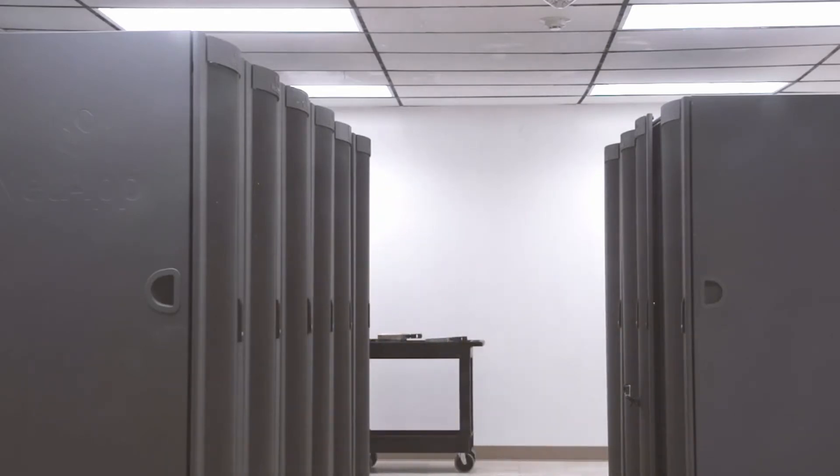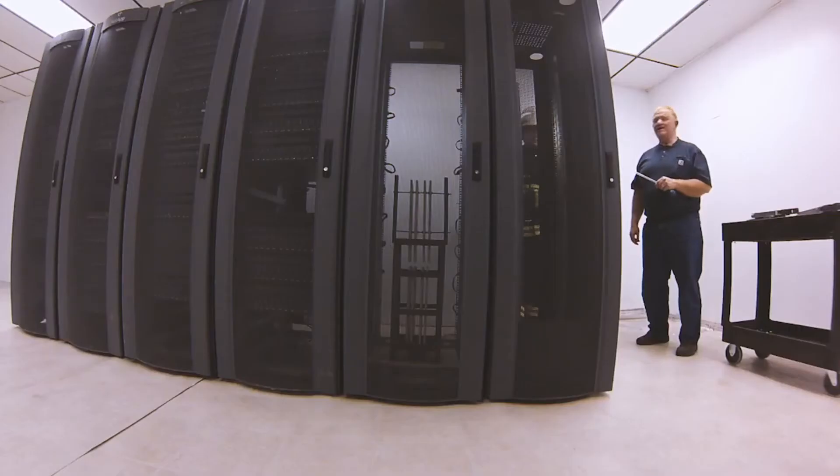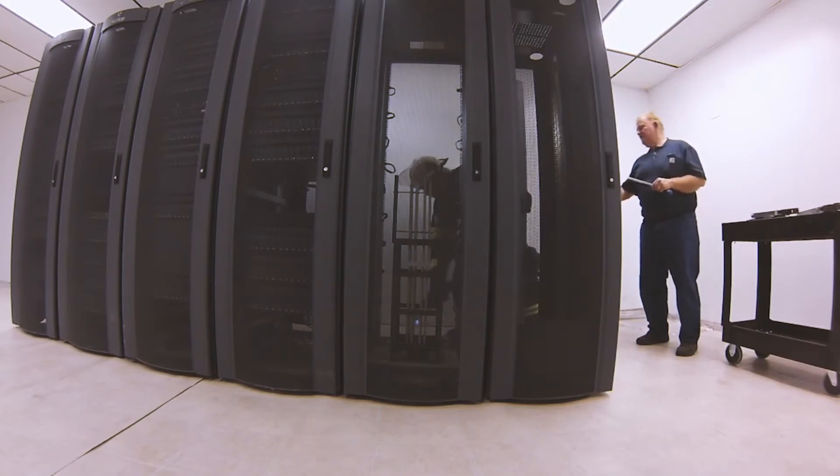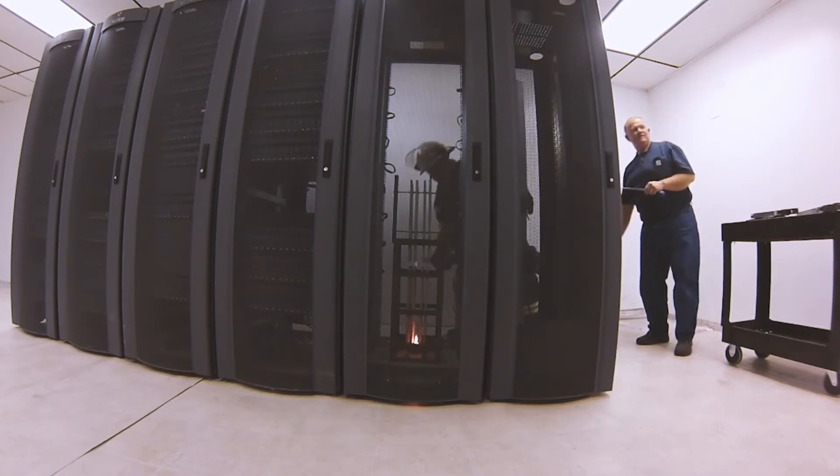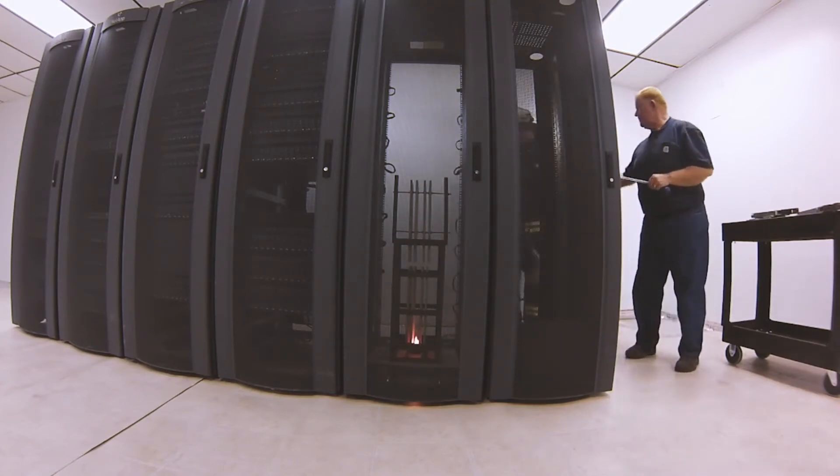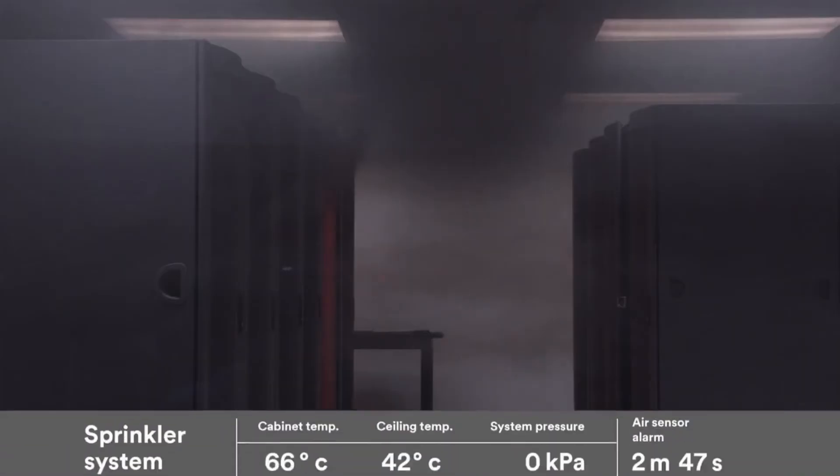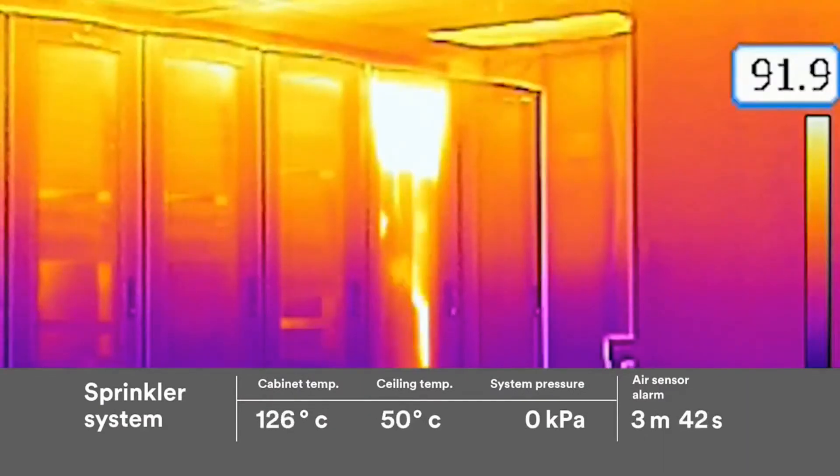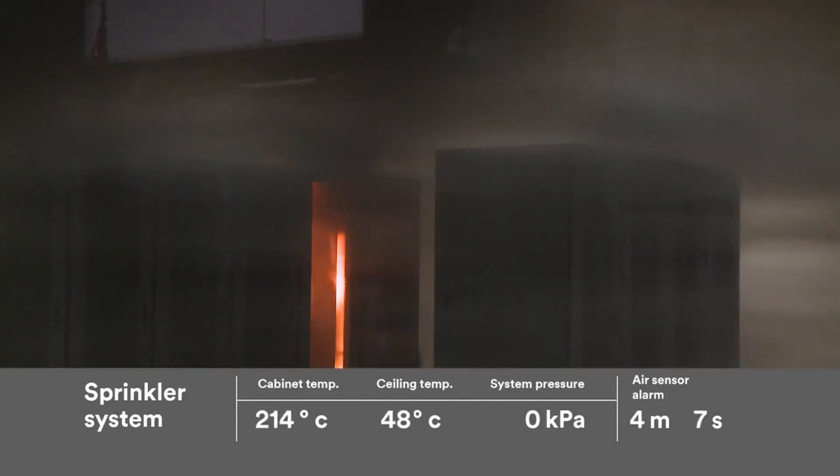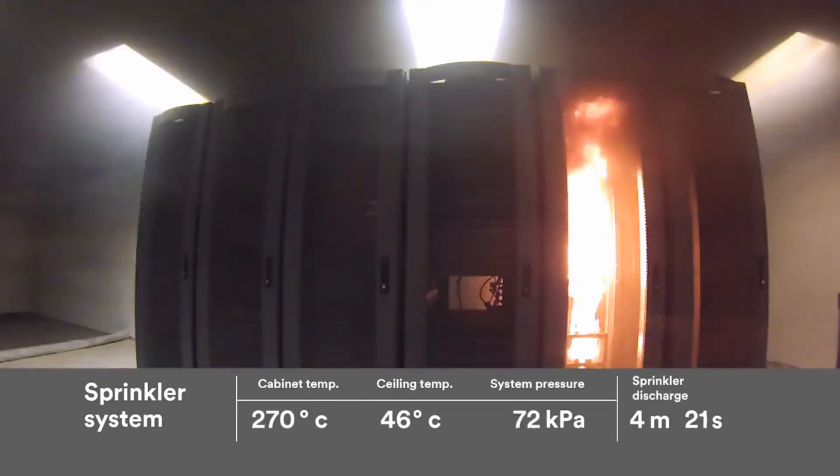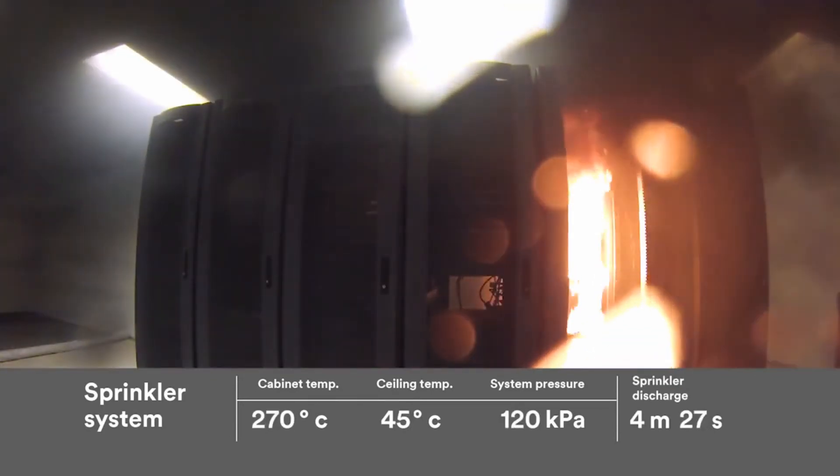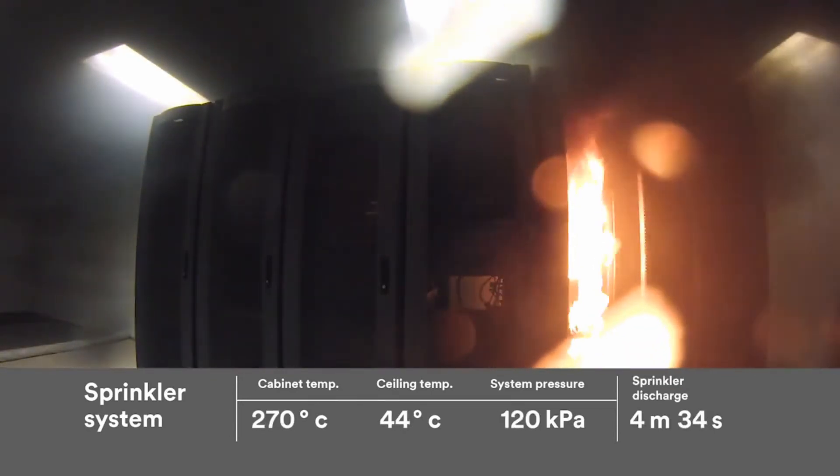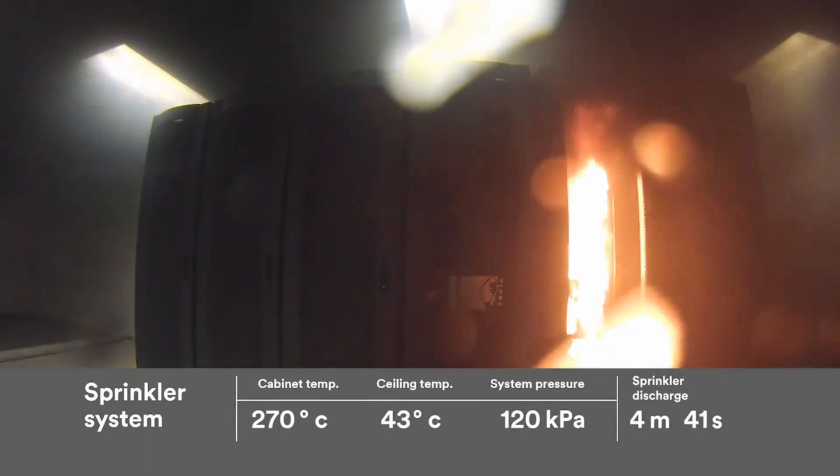Now we're ready for the water discharge test. In the same fire scenario as before, plastic sheets inside the same server cabinet are ignited and technicians leave the room. Two minutes pass, then three minutes. The heat of the fire rises to 91.9 degrees and dense black smoke fills the room. Finally, after nearly four minutes, the sprinkler heads discharge. For 11 minutes, the room is deluged with water. Even so, the fire in the cabinet stubbornly refuses to go out.